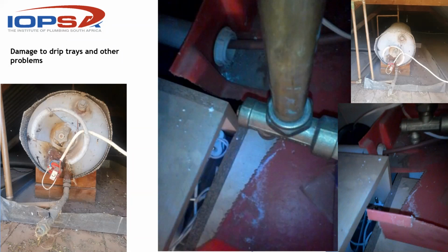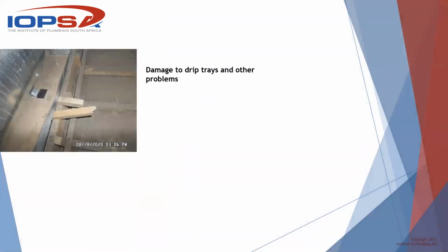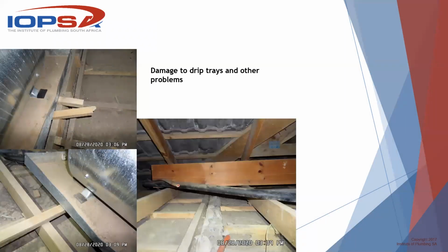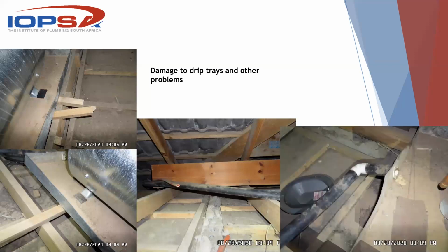No, but in all seriousness, guys, this is about drip trays. Have a look at that, because he installed it in a cupboard. And it's just, I mean, what's the use? What is the use? Okay, some more examples. These are more recent ones that I took personally. Drip trays being supported in a ceiling space with one batten.